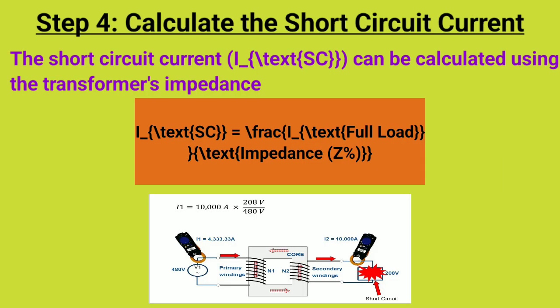Step 4. Calculate the short circuit current. The short circuit current I_SC can be calculated using the transformer's impedance: I_SC equals I_full load divided by impedance percent, where impedance percent is divided by 100 if provided as a percentage.